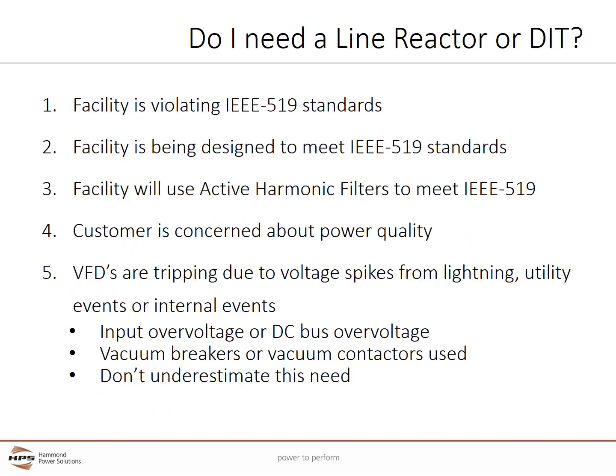There are some situations where a line reactor or a DIT aren't just suggested but are really truly needed. First of all, if the facility is being fined for violating IEEE 519 standards by the utility, typically the user will ask for a solution, and depending on the severity, line reactors and DITs can provide harmonic mitigation. Reactors and DITs may be a solution or part of the solution. Reactors typically provide the least expensive method to remove harmonic currents. DITs cost more but are still competitive with other technologies for cost per amp of harmonic current removed.